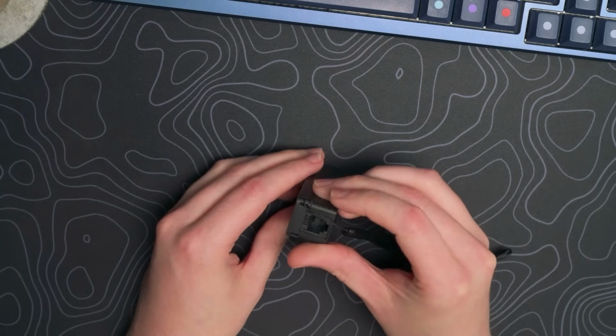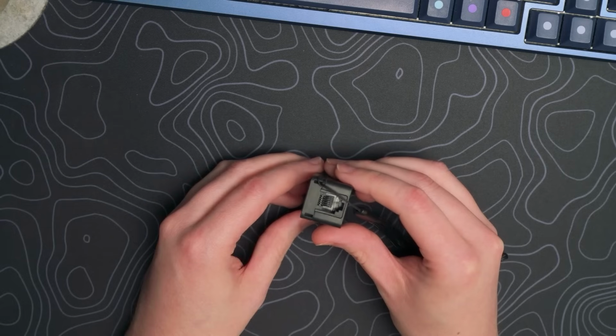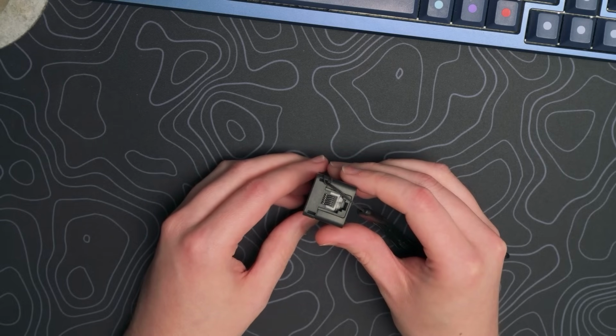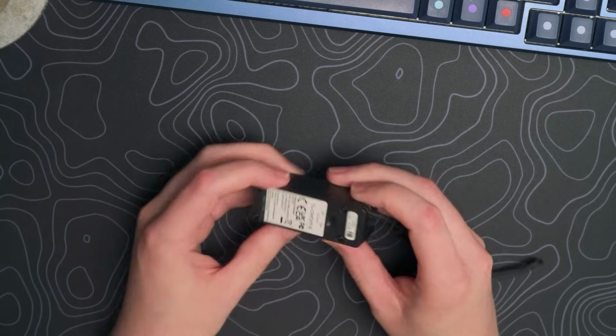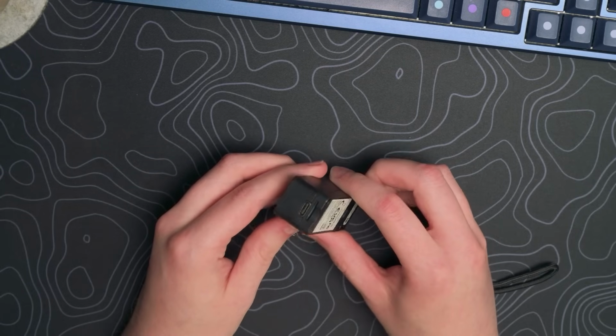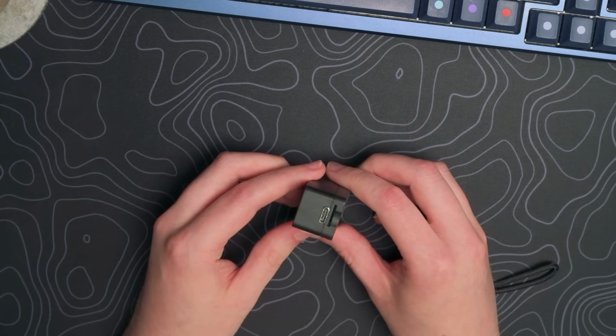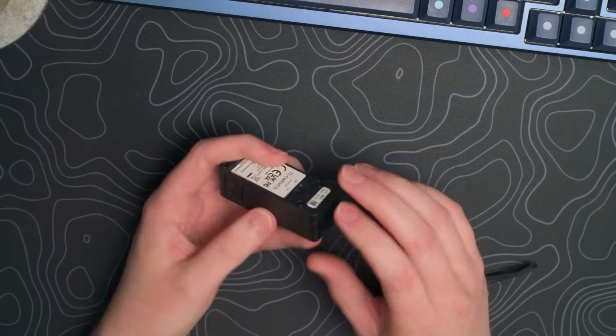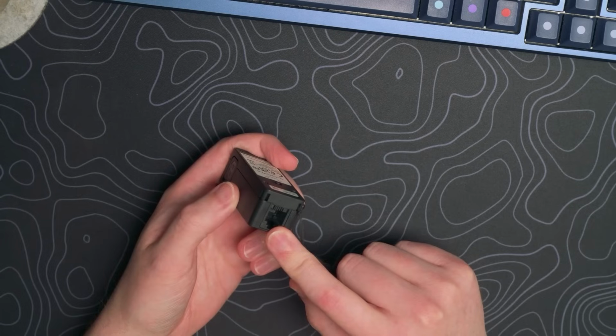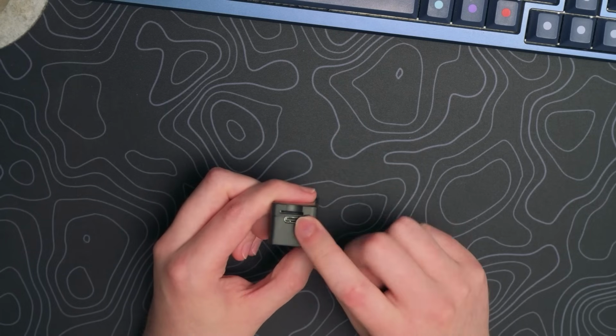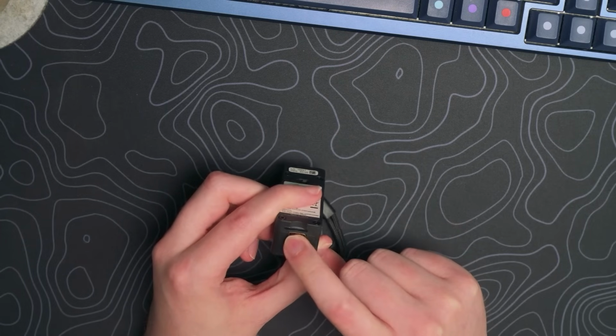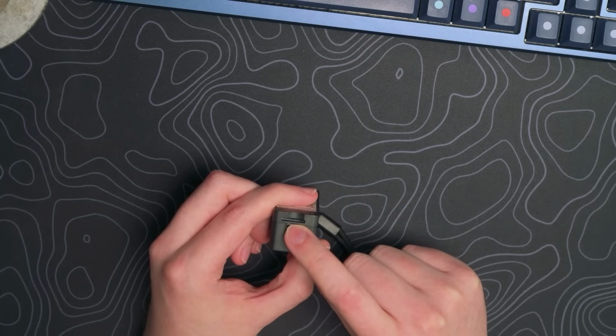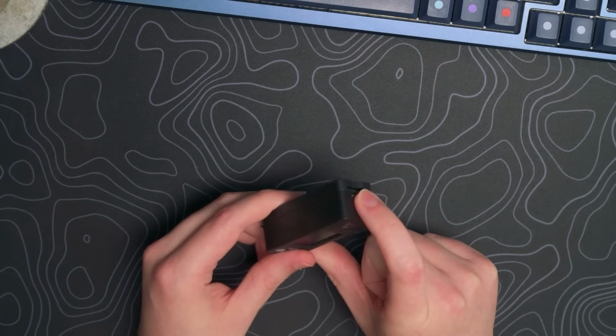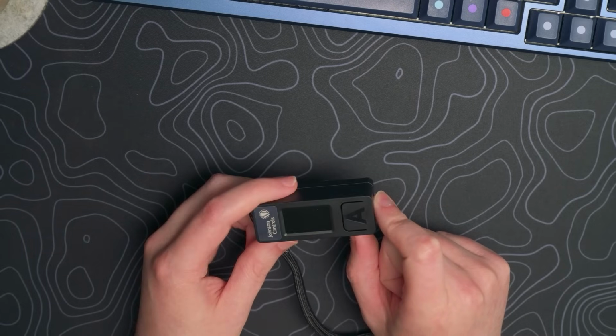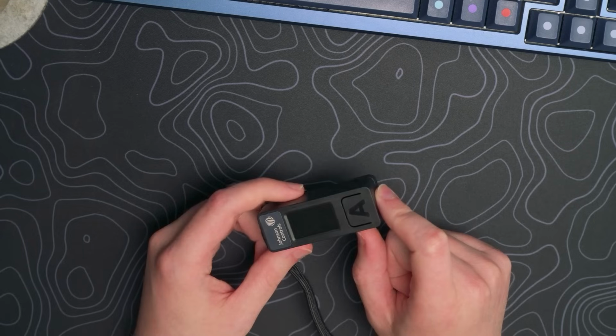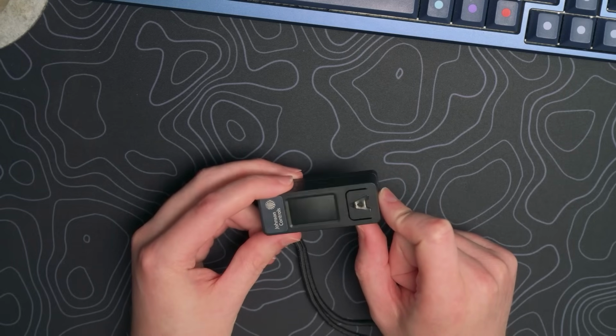You can see on one end we've got our RJ11 that lets us plug into the Johnson controllers. You obviously can plug in on the FC or the SA bus. And then on the other side, we've got a USB-C connector that you could use to power it directly without getting your power through the RJ11 when you plug into the controller. And we also have a micro SD card holder here that we can use to do some diagnostic logging and things from our BACnet network that we're talking to. So let's bring in a controller here and plug it in and have a look at the interface.